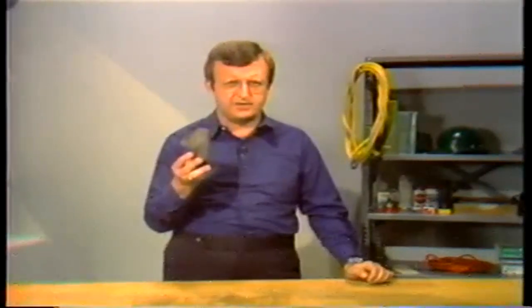There are still four other water wall problems we need to talk about: clinker damage, flame or fuel impingement, trouble with burner openings, and trouble with inspection doors. Clinker damage occurs when clinkers high in the furnace fall and hit the water wall tubes at the bottom of the furnace. This causes tube bending, crimping, and denting, and it also wears away the tube metal.